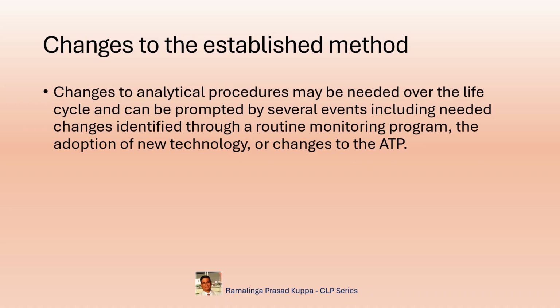Changes to analytical procedures may be needed over the life cycle and can be prompted by several events, including needed changes identified through a routine monitoring program, the adoption of new technology, or changes to the ATP.